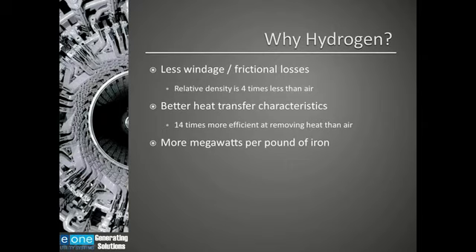Why hydrogen? Well, hydrogen provides less windage losses or frictional losses. Hydrogen is four times less dense than air, which means you can spin the rotor in a generator with hydrogen a lot easier than you can spin a rotor in an air-cooled generator. Hydrogen has better heat transfer characteristics. It's 14 times more efficient at removing heat than air is. The bottom line is that you will get more megawatts per pound of iron if you're using hydrogen as a cooling gas.